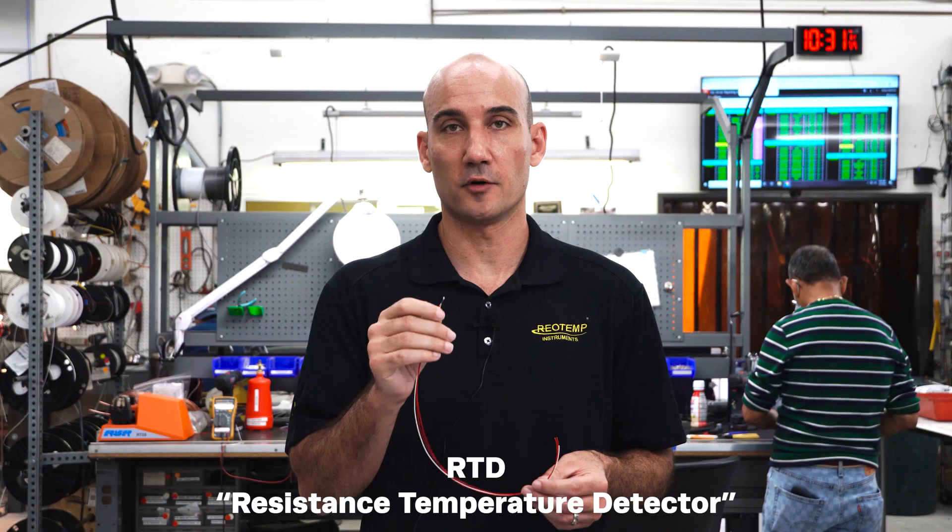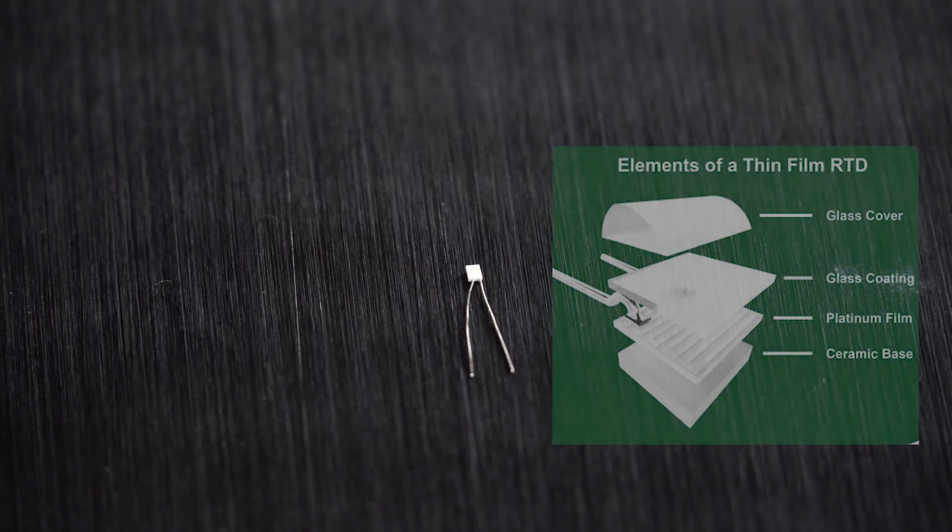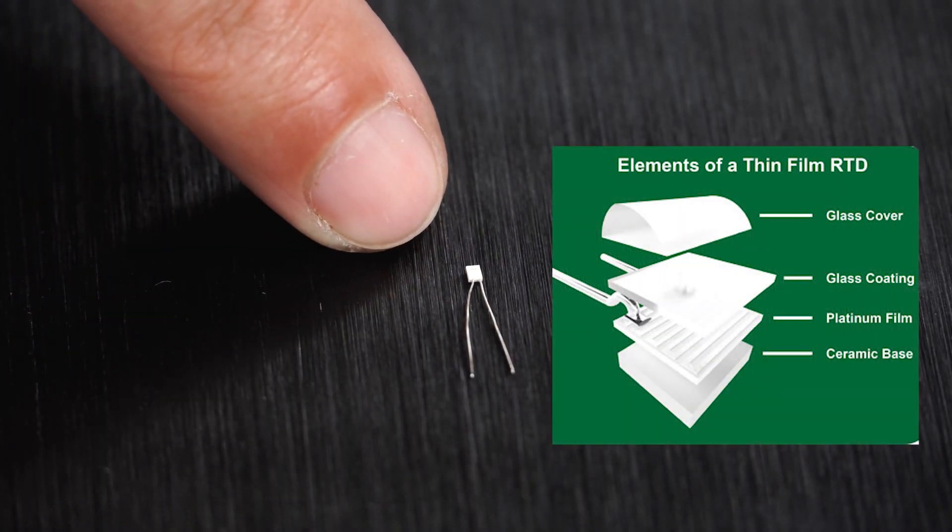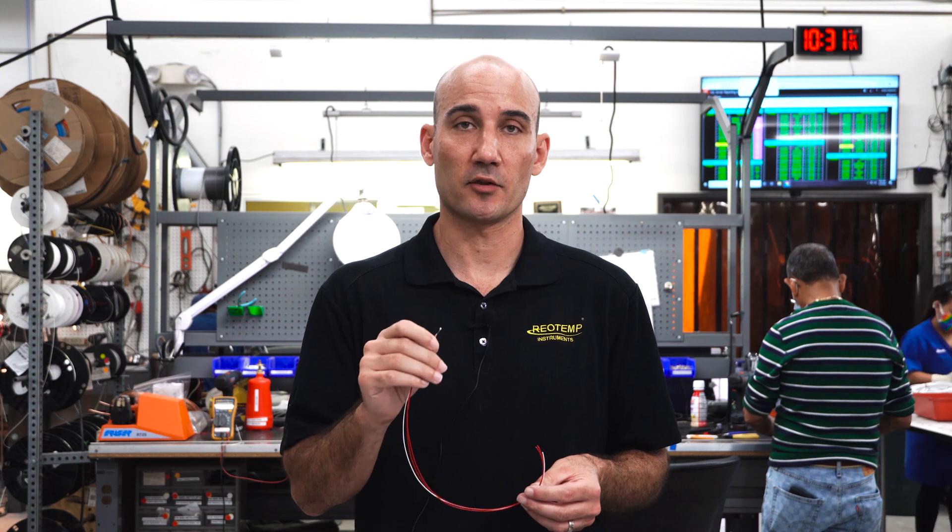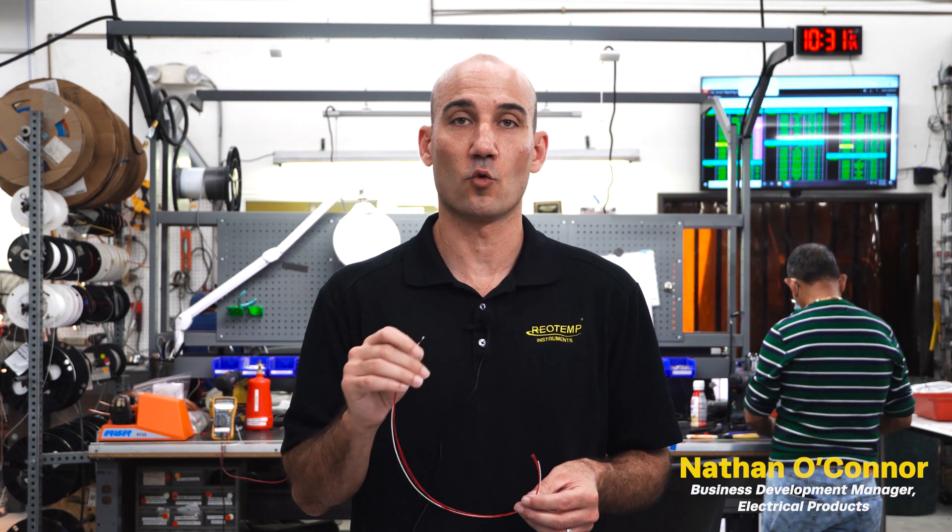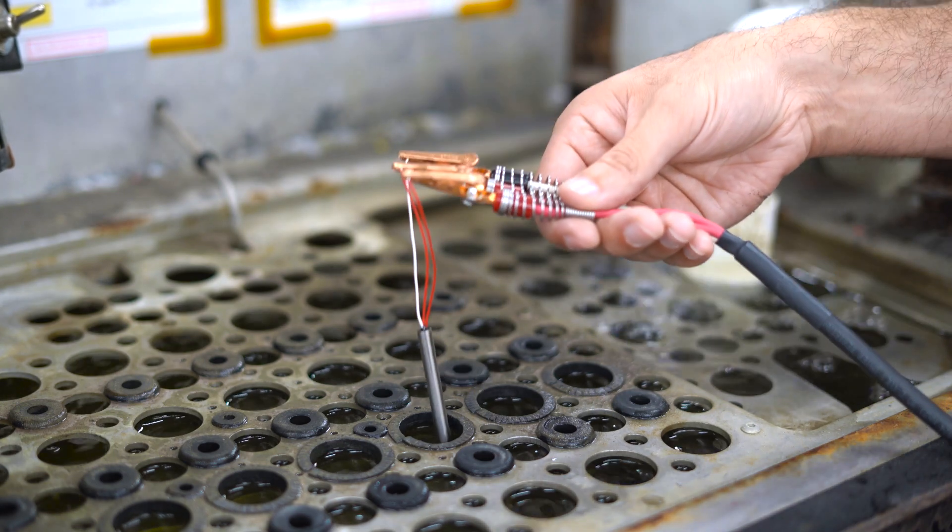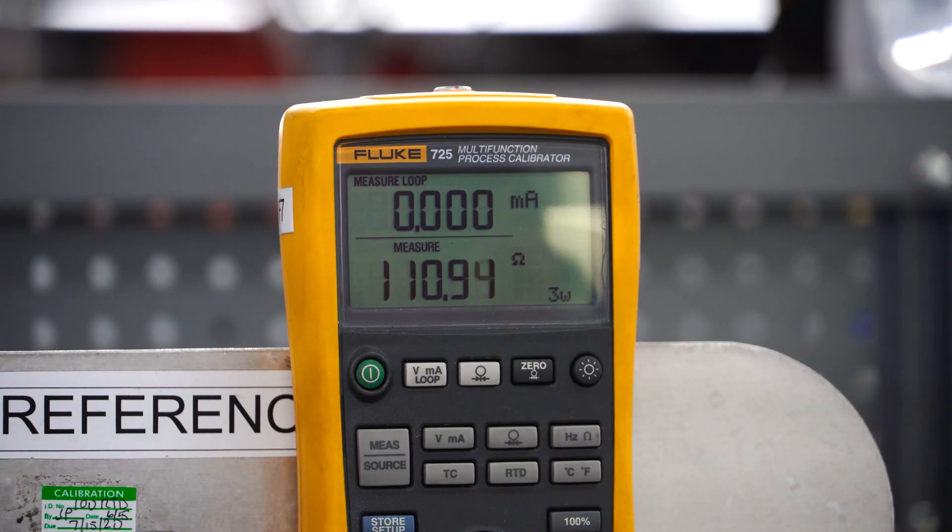First let's understand how an RTD works. This is a thin film 100 ohm RTD. Inside the ceramic housing there's a thin layer of platinum. That thin layer of platinum has a known resistance of 100 ohms at zero degrees Celsius. As the platinum heats up, that resistance is going to change in a very predictable and accurate way.